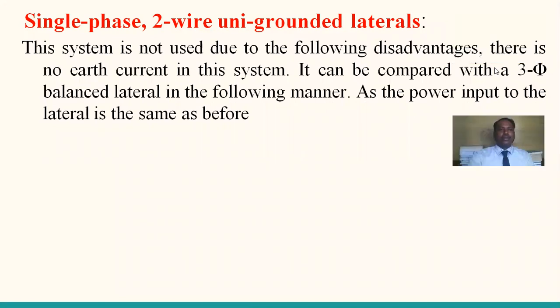So this system is not used due to the following disadvantages. There is no earth current in the system. Earth plays a crucial role in the electrical system. Due to one conductor being uni-grounded, the major problem is that there is no earth current, otherwise no ground current. Due to this drawback, the system is not commonly used.